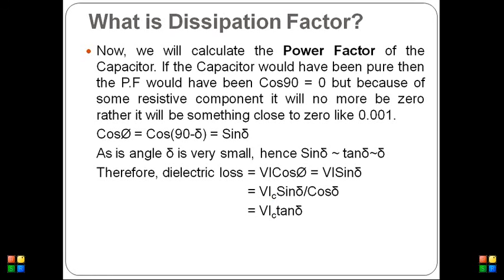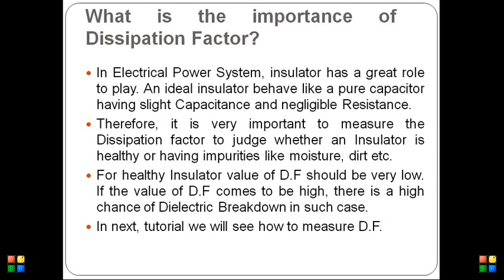The importance of dissipation factor is significant in electric power systems, where insulators play a great role. An ideal insulator behaves like a pure capacitor with slight capacitance and negligible resistance. Therefore, it is very important to measure the dissipation factor to judge whether an insulator is healthy or has impurities like moisture or dirt. If an insulator has such impurities, it will have more resistive leakage, meaning increased loss and a chance of dielectric breakdown. If the measured dissipation factor is very low, the insulator is healthy; if it is high, the insulator is not healthy.